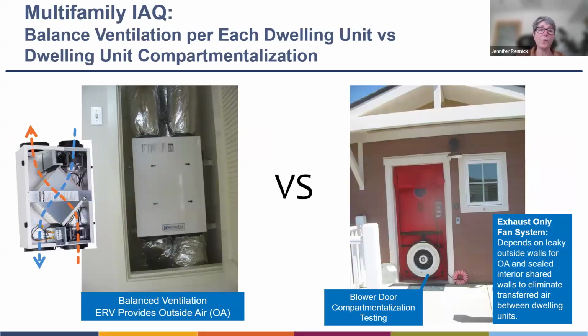Now, currently, with multifamily, there is a way to get out of doing blower door or compartmentalization testing that requires a HERS rater to come out and test these buildings. In lieu of doing all that testing, you could install a balanced ventilation system, and that got the builder and the HERS rater out of doing that testing. Okay, that's going to change in 2025, but that's currently how we have it. If you do an exhaust only fan system, then you're going to do the blower door testing, extra testing.